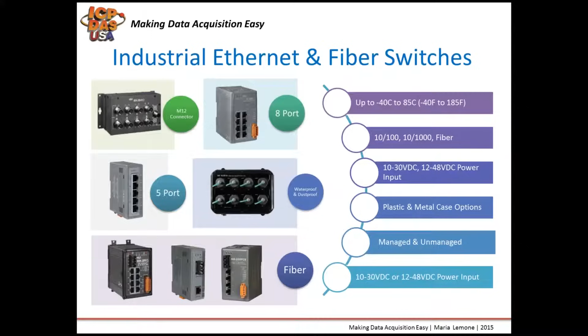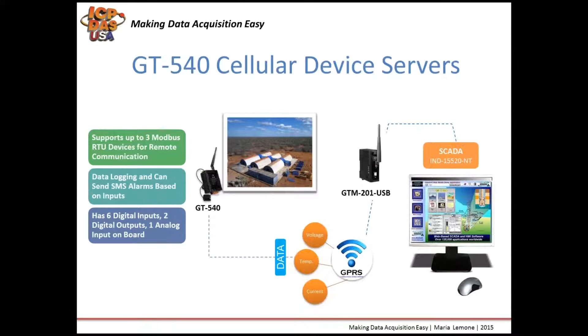GPRS remote terminal device servers with data acquisition, like the GT540-3GWA, communicate over the cellular network and bring data from Modbus devices back to SCADA systems over the internet. They have 6 digital inputs, 2 digital outputs, and 1 analog input on board. They can log data on a micro SD card and are widely used in M2M machine-to-machine applications for getting data from machine and automation systems back to a PC. They can be used for truck tracking systems where you can see the location and temperature in refrigerated trucks transporting goods, or for reporting back the contents of a vending machine.